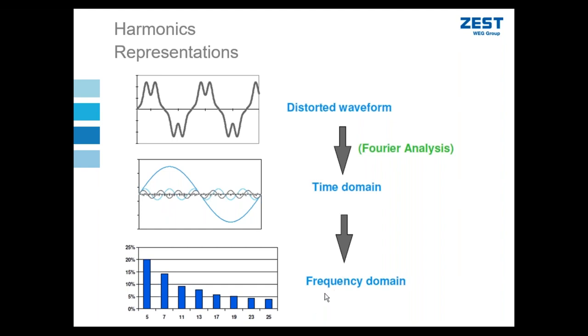Then we can go one step further and represent it in the frequency domain. So, for example, if we look at this distorted waveform, we would divide it, let's say, for example, the fifth harmonic, we show its amplitude is 20%. That means that the harmonic frequency is five times the frequency of the fundamental. So let's say, for example, this fundamental frequency is 50 hertz. Then the fifth harmonic would be the waveform that is at 250 hertz. Basically, it crosses the zero midline five times on every cycle of the fundamental wave. And we can represent that in the frequency domain as shown.